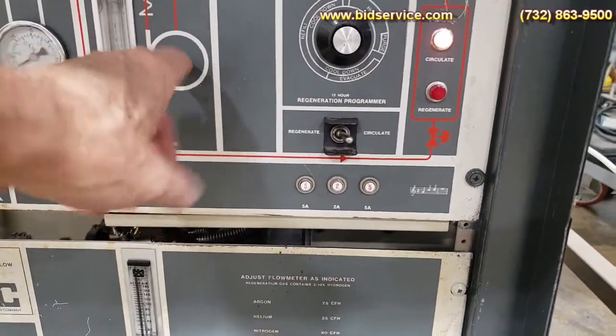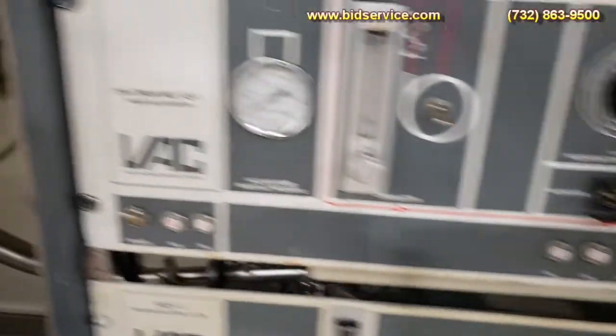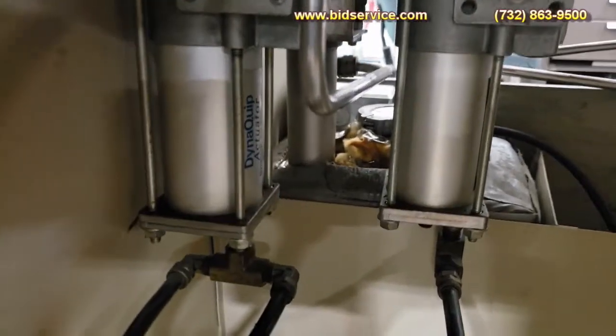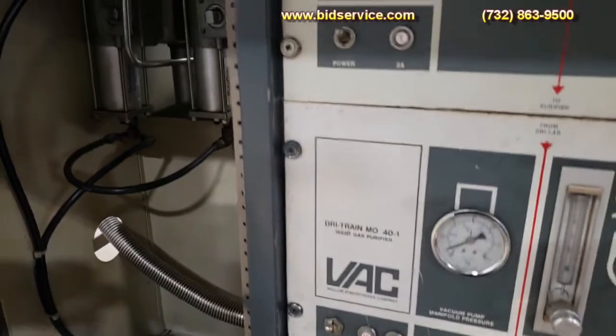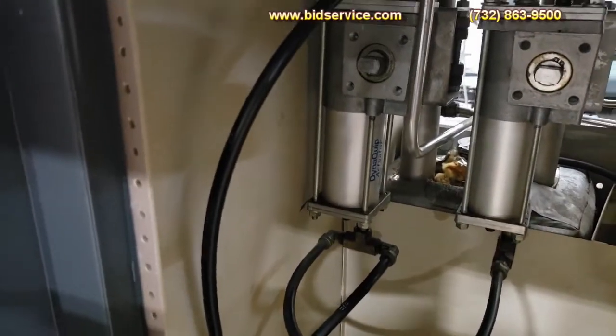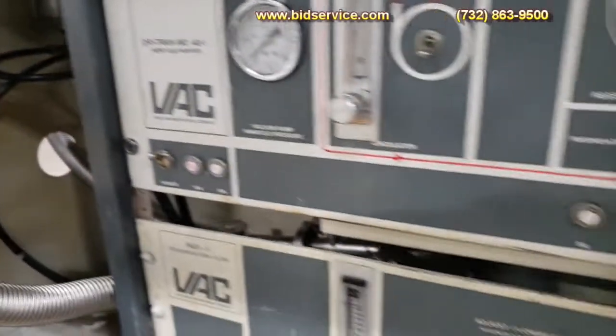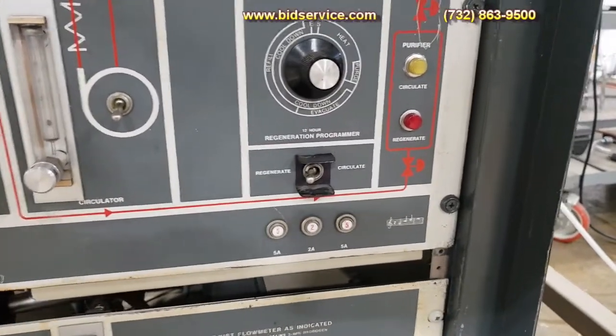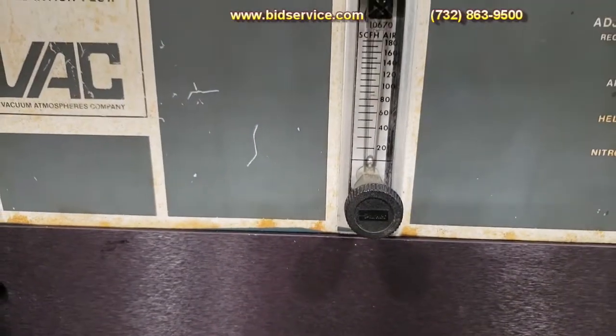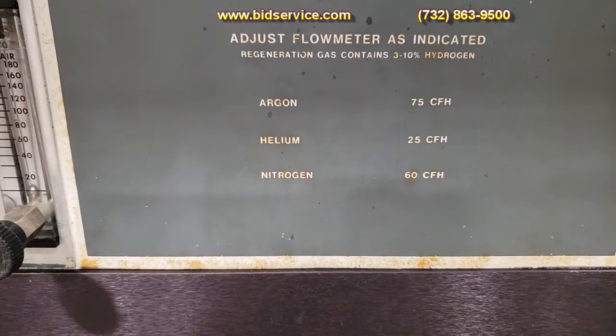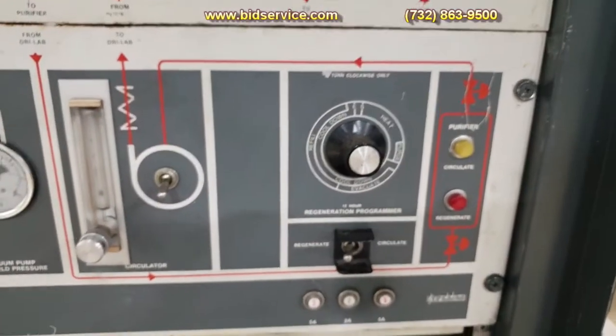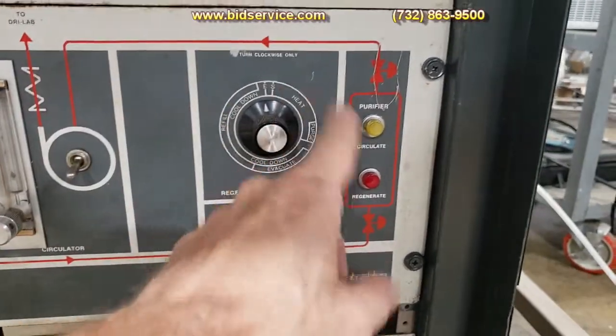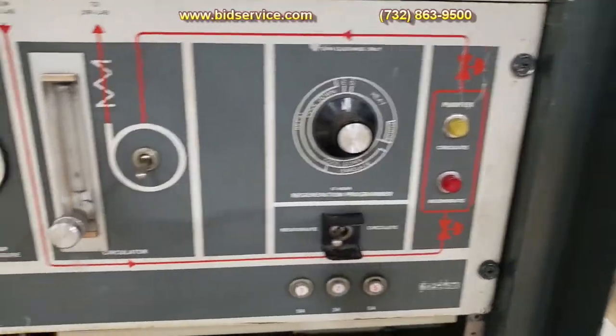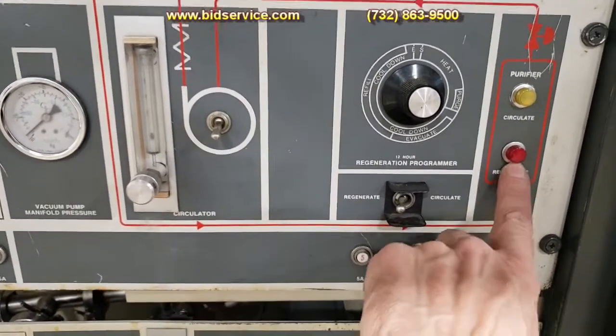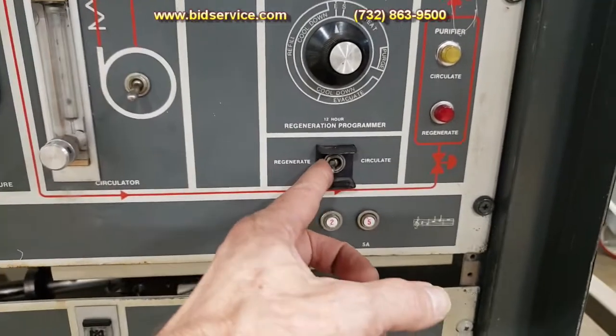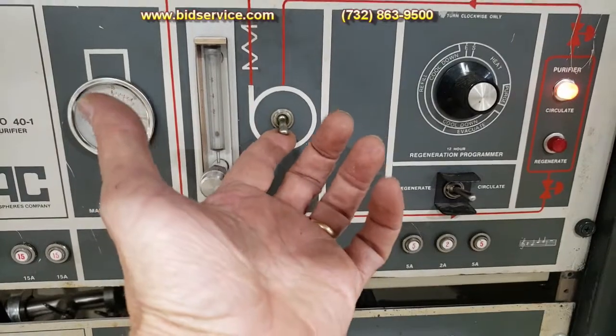At this point, if you want to switch over to do a regeneration, you can hit this switch here. What that's going to do is, there are 2 pneumatically controlled valves sitting right on top of the purifier, and they're going to close when I hit the regen. You can see they turn 45 degrees. In order to start a regeneration, you want to make sure you have your forming gas connected and set to the right flow, which you set down here. So for nitrogen, you'd want to set it to 60 on the gauge. And then you just turn this valve to S. It'll start. It takes about 12 hours to go through a heat and purge and evacuation and cool down process. This is all explained in the manual. When it does start, you'll see the red regen light turn on. But we're going to switch right back to circulate and turn our circulation and the blower on.